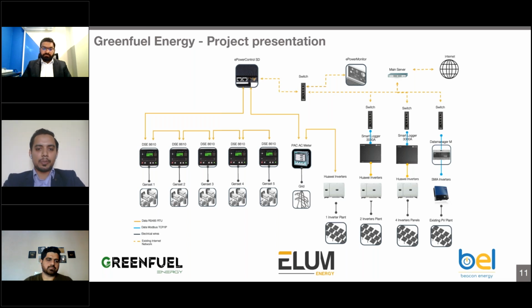As you can see in this presentation, there are 5 gensets over there, and they were communicated with each other, synchronized with the DeepSea controller, and at the end connected to the Elum controller. On the other hand, there are 3 segments of Huawei inverters, shown with the inverter shed, collectively 8 inverters. These were communicated with each other through daisy chain, and at the end through data loggers into the port of the Elum controller.